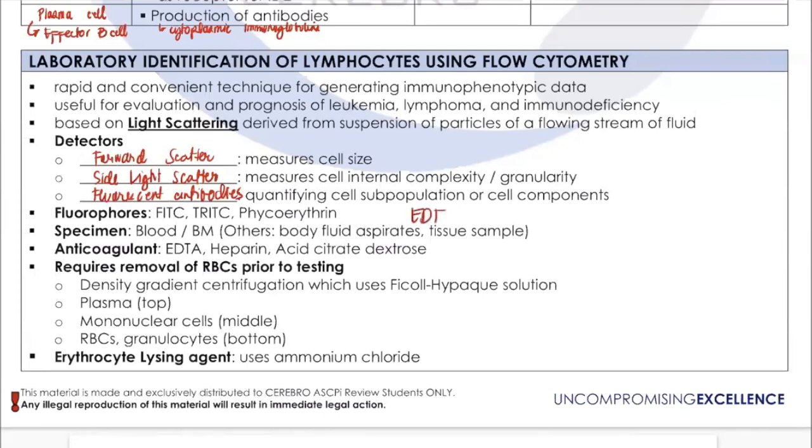However, if you use EDTA for your blood samples, you have to process them within 30 minutes.